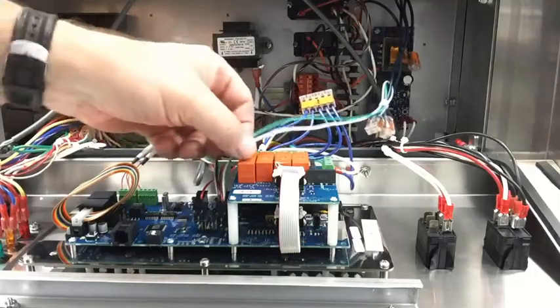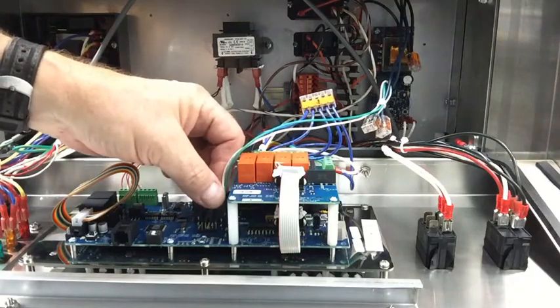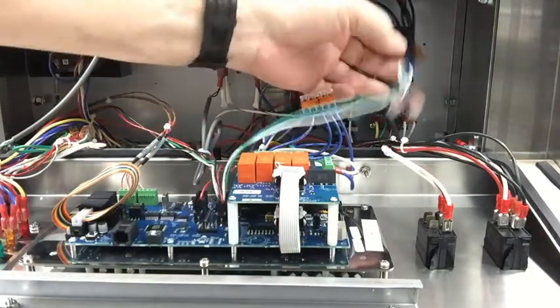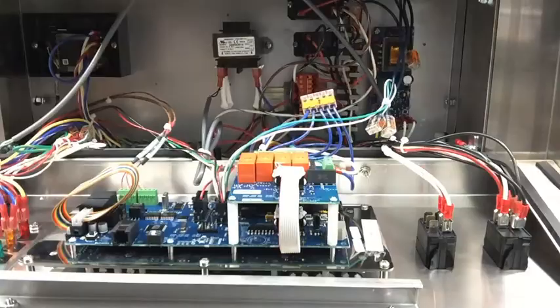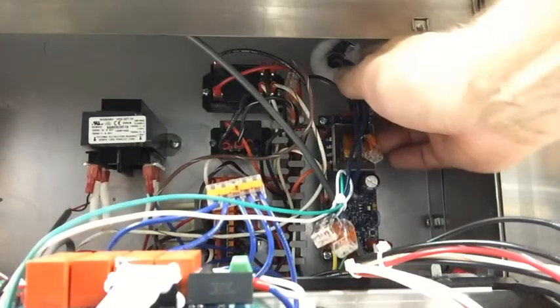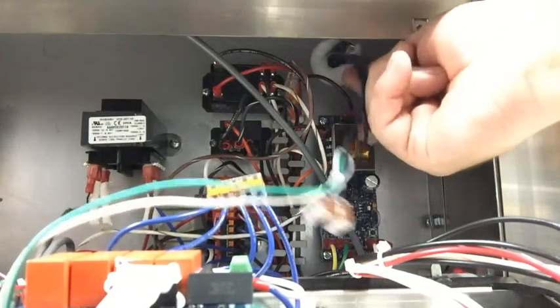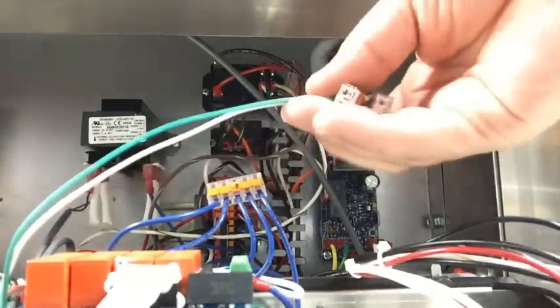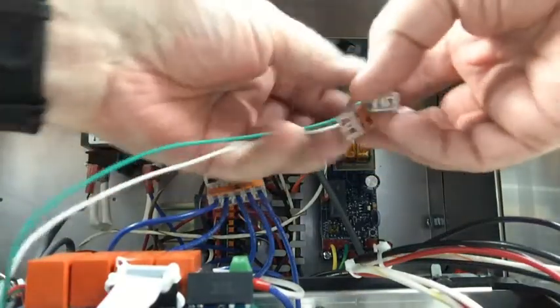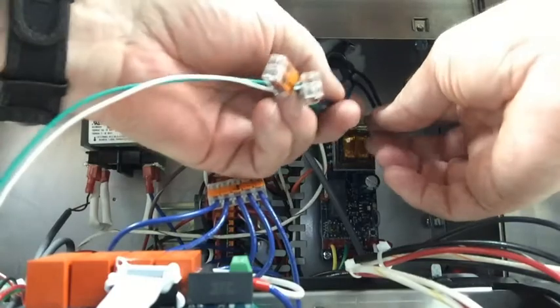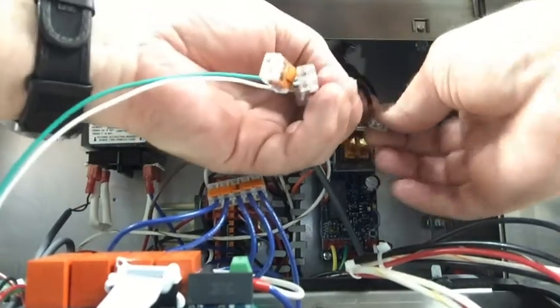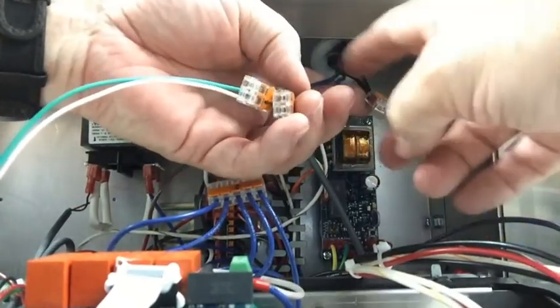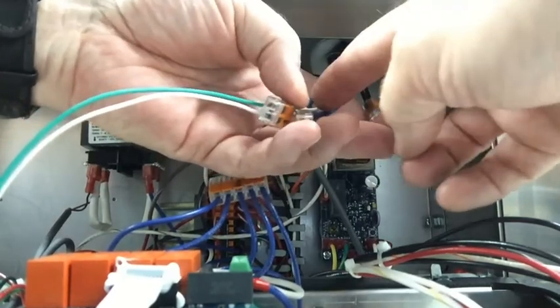This green and white wire, they're coming from the 16 pin connector. Those two are going out to your drain switches. Now you'll notice right up here where my finger's at, these wires right here, these are going to your drain switch. So there's actually 2 switches in there, and they're wired normally open. One of these blacks goes to a switch and a blue, and then a black and a blue.